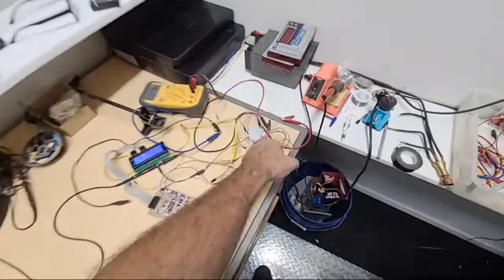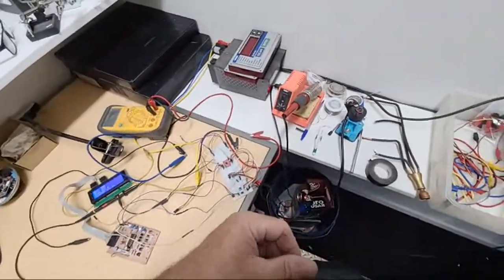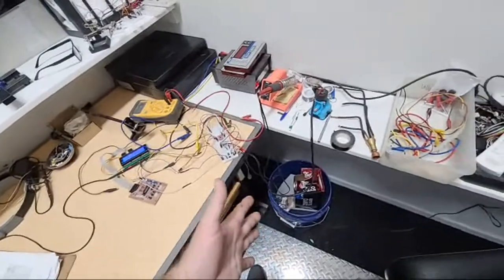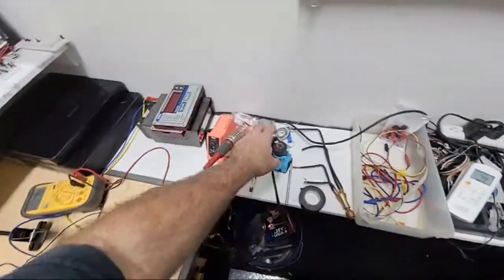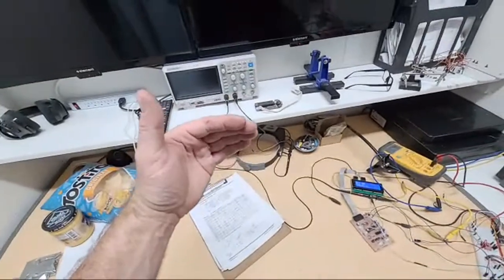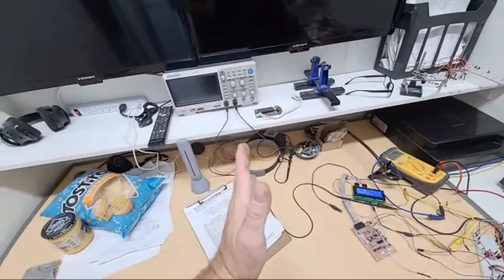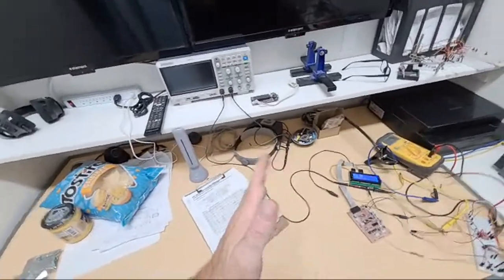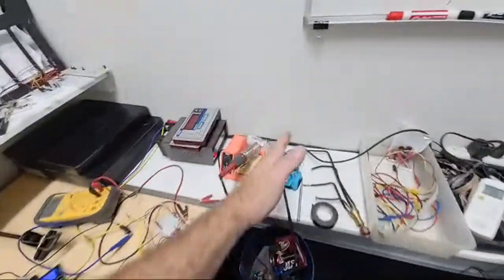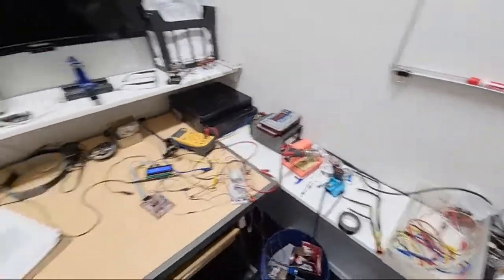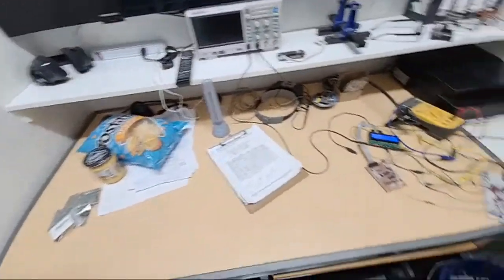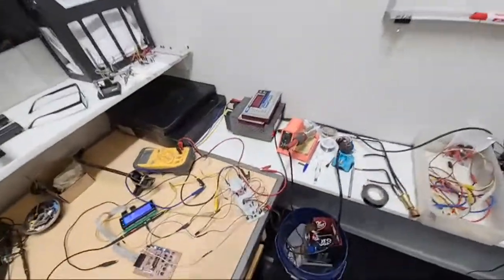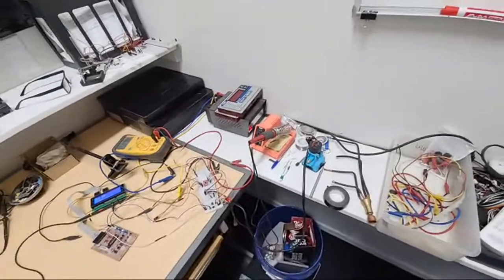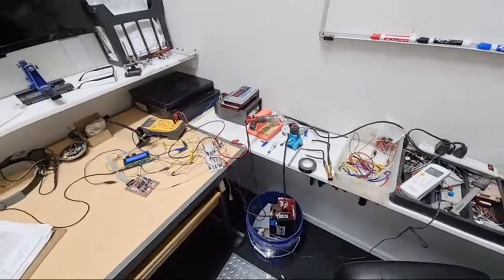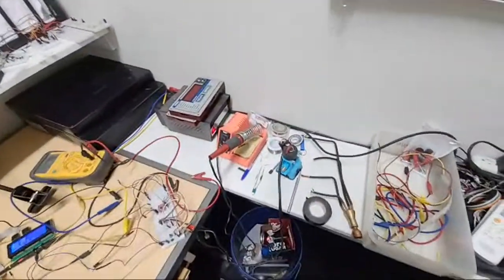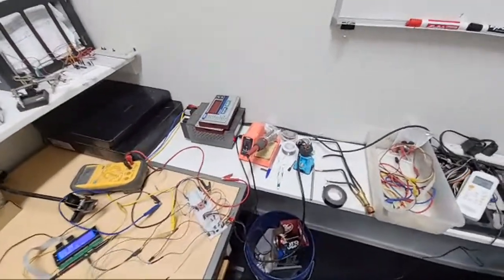I could change this to do full steps, half step, quarter step, eighth step, 16th step, which is where you modulate the voltage between each of the poles of the motor, start increasing one while you're lowering the other, and then you shift in between the magnetic poles of the motor to get more increments. But I don't need that. I'm not running a servo to run some precision mill or anything like that. It's just winding an EXV open and closed. 255 possible points between open and close, I think, is enough for what I'm doing. They're probably doing a little more resolution than that from the factory, but that's what I'm going to do.